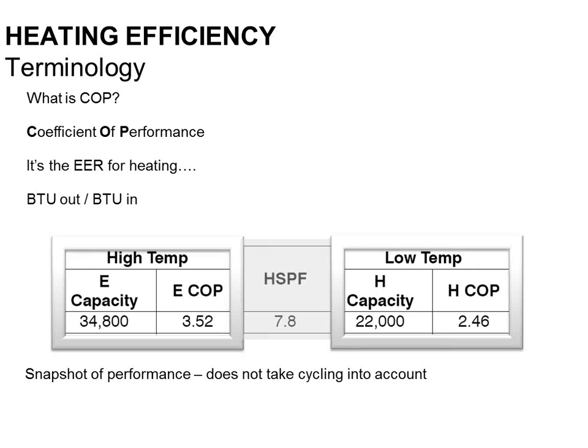It doesn't mean it's the cheapest to run, right? Because I might have high electric costs and low gas costs, and I'll show you that in a second. But it means it's the most efficient thing that I could possibly do. I guess the only way to be more efficient than an air-cooled heat pump is to have a water-cooled heat pump. And the only thing more efficient than a water-cooled heat pump is a geothermal water-cooled heat pump, right? In all cases, those are heat pumps, though.